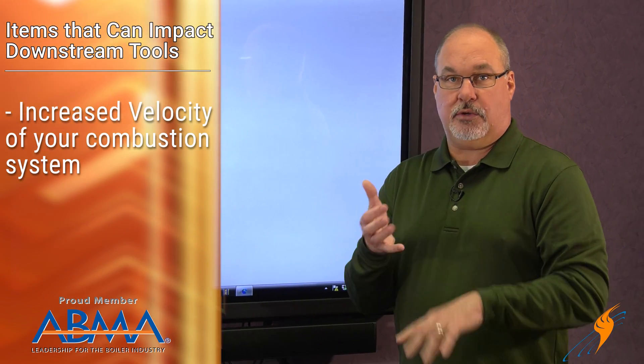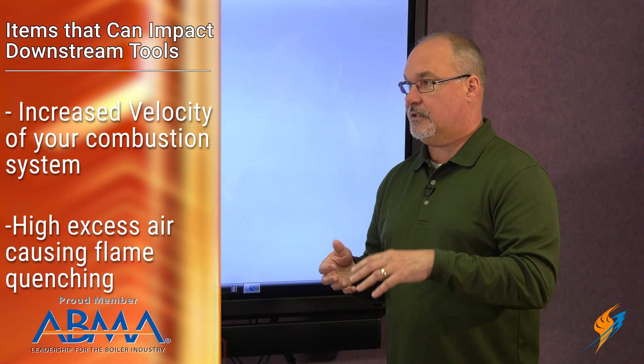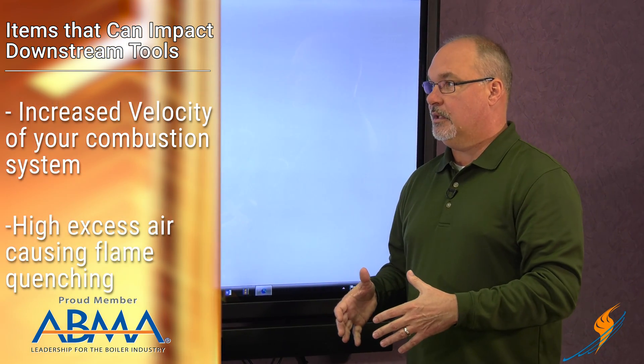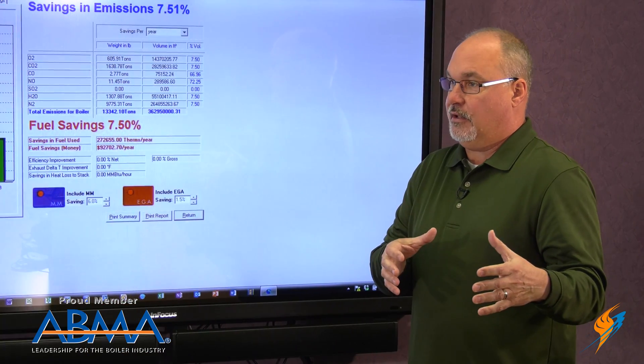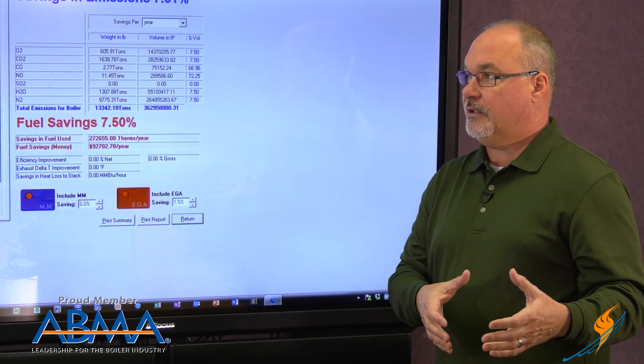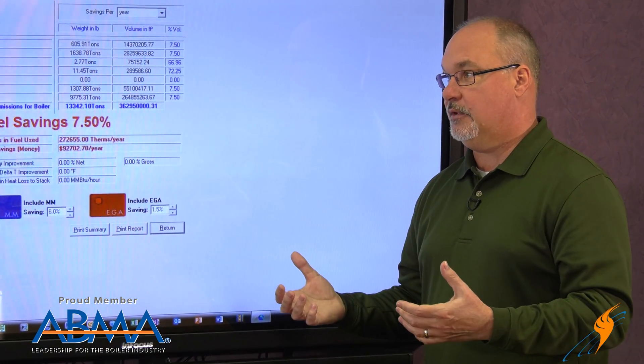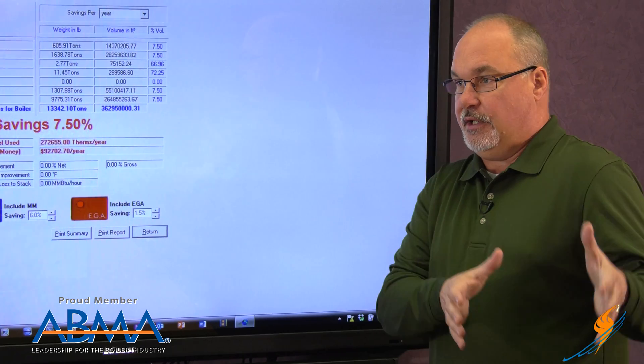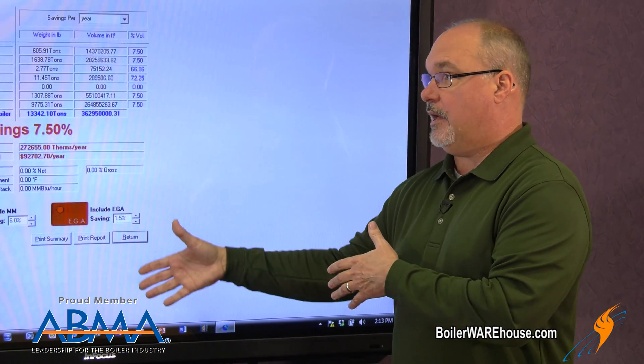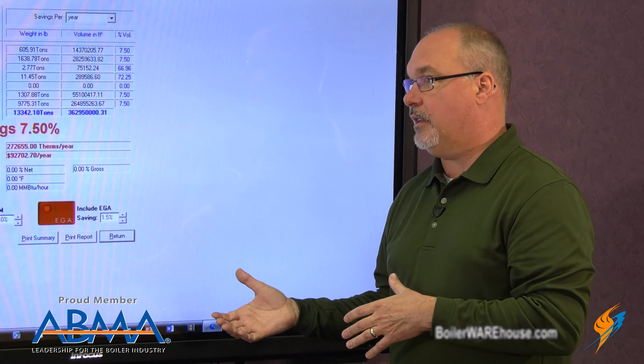It could be increased velocity of your combustion system, it could be high excess air causing flame quenching and causing the furnace to cool — and those things are anti-heat exchanger. It could also be bad combustion producing CO and just wasting fuel. By getting those things corrected and putting the front end in the right position, we improve the process and allow all of those back-end tools to do the job the way they were designed.